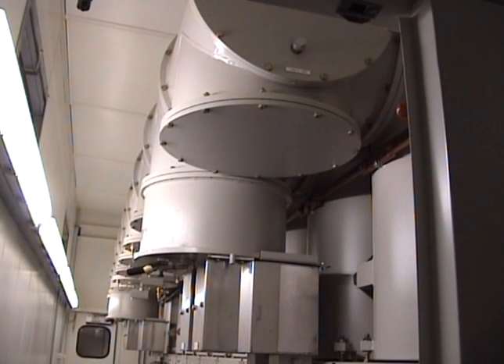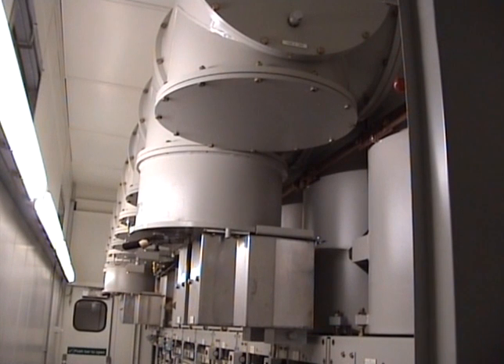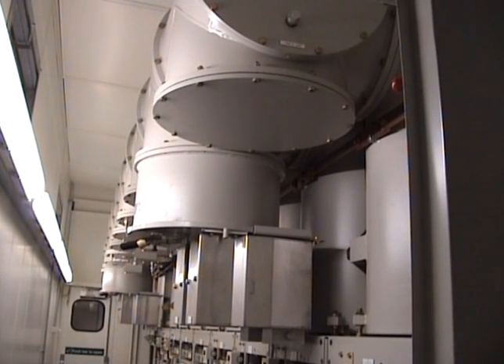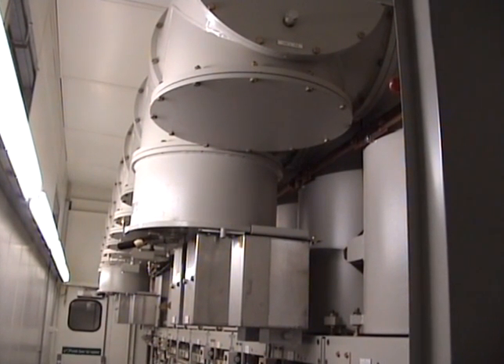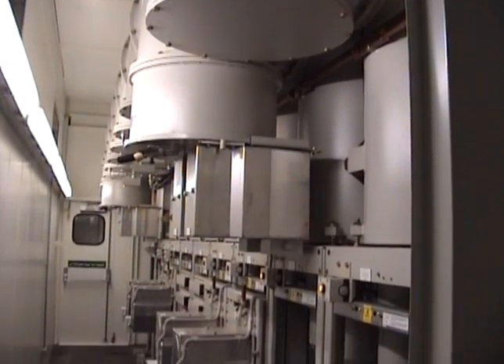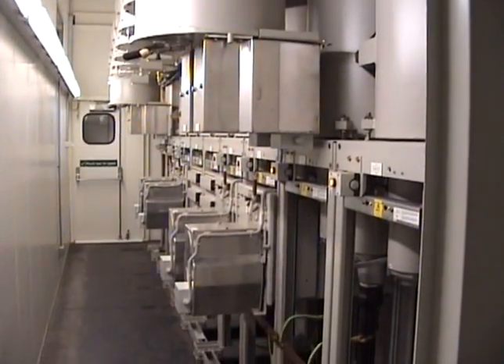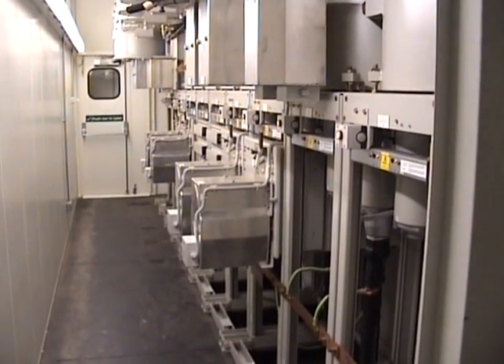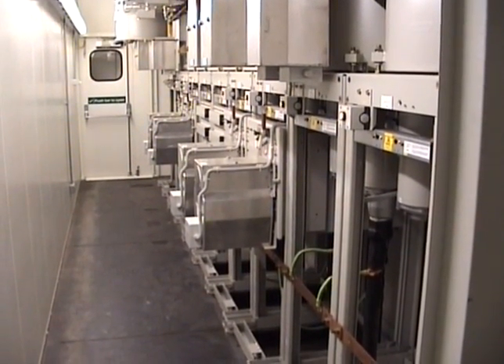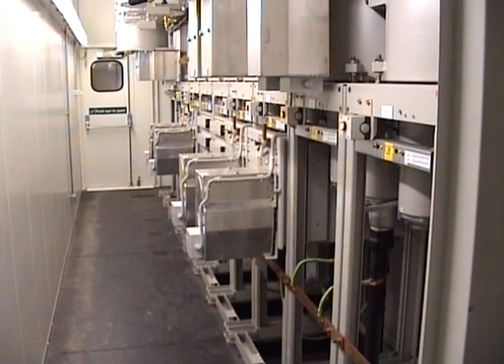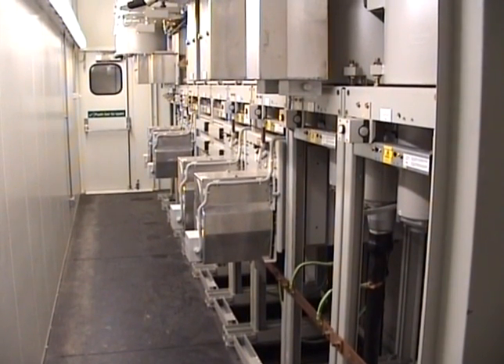This is the rear of the switchgear, showing the bus bar chamber containing the plus and the minus bus bars, one of which goes to the catenary, the other of which goes to the auto feeder. The bus bar contains SF6 gas as an additional insulating medium. Down below we see the outgoing circuit breaker connections and the VT voltage transformers.